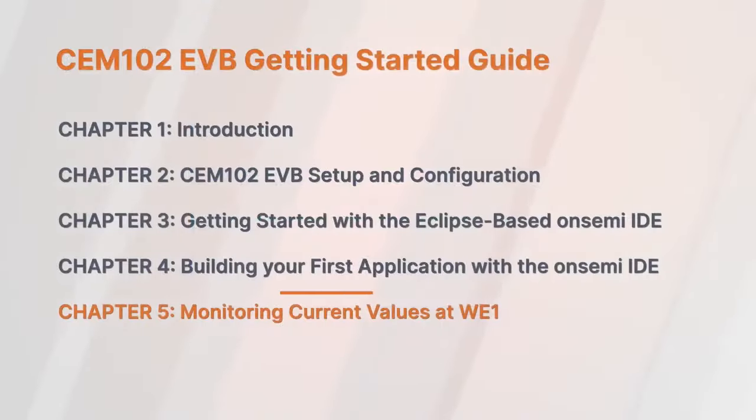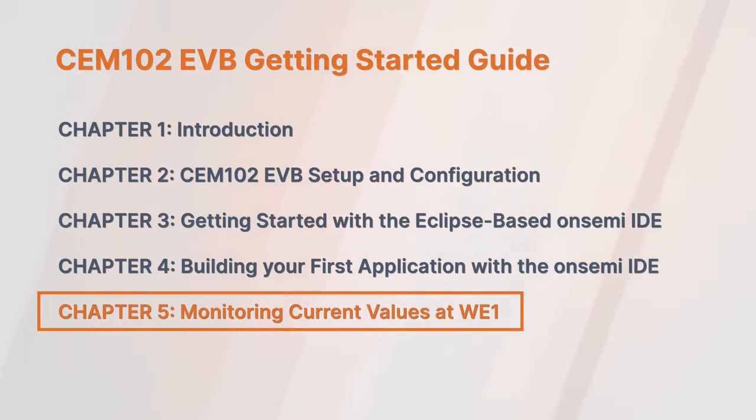Now let's review a methodology to measure current values at the WE1 channel using the CEM-102 Basic application. We use the Tera Term software for monitoring the values. Please note the location of the WE1 and ground pins used for measuring and monitoring current values.